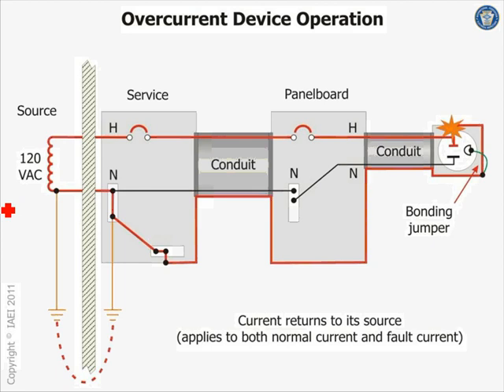But let me tell you when this becomes very powerful. What happens if you lose a neutral here? Well, in this system, it doesn't matter, because if you lose a neutral, you lose the whole circuit. But if that was a split phase system, there's another phase here, and you lost your neutral here, right? And you have a ground fault, your ground fault will all go right through Mother Earth. We're not supposed to, but that could be kind of your second line of defense at one time.